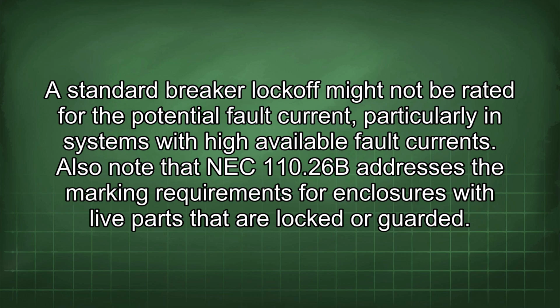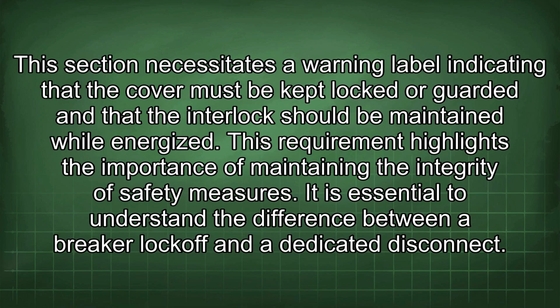110.26(B) addresses the marking requirements for enclosures with live parts that are locked or guarded. This section necessitates a warning label indicating that the cover must be kept locked or guarded and that the interlock should be maintained while energized. This requirement highlights the importance of maintaining the integrity of safety measures.